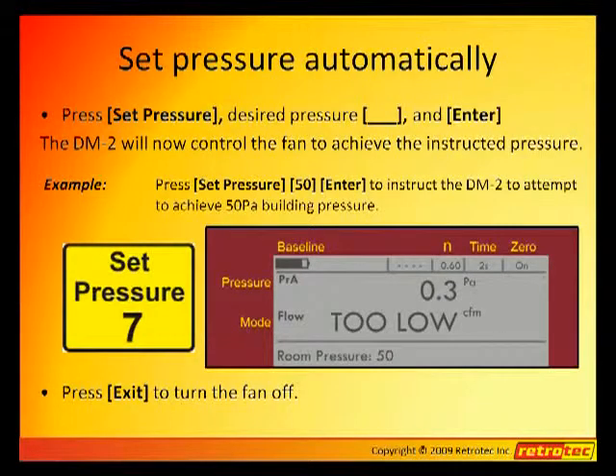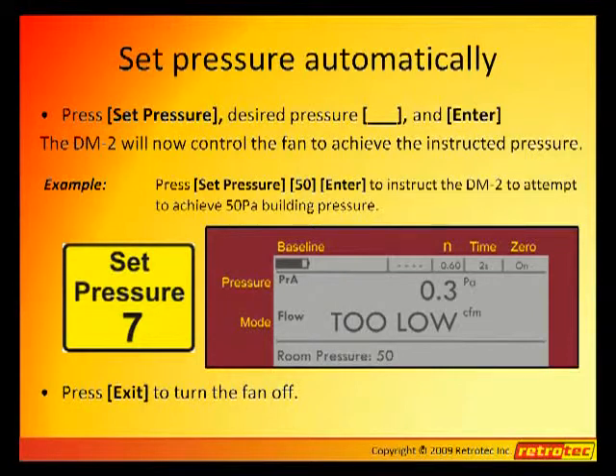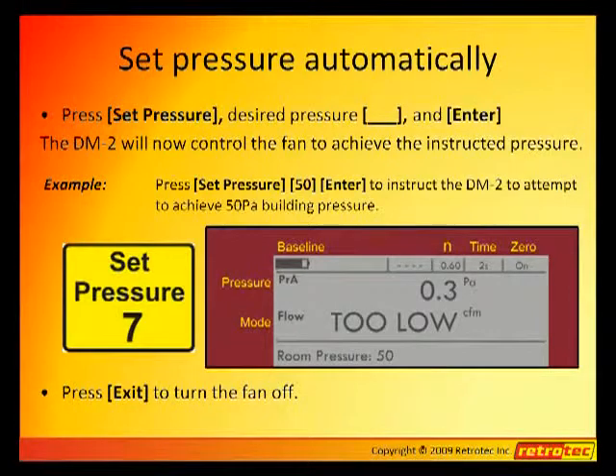The room pressure can be set using the gauge by simply pressing Set Pressure, then the desired pressure difference, followed by the Enter key. This activates the Jog feature, which can then be used for Set Pressure adjustments.